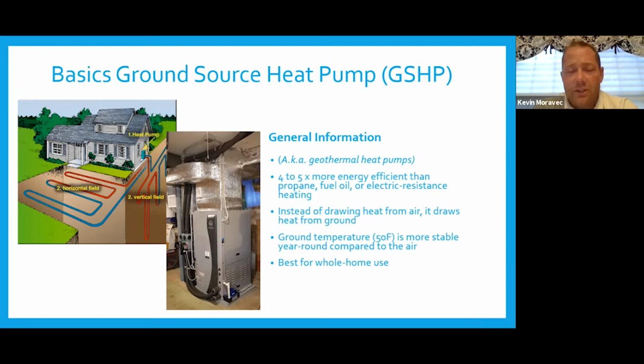The efficiency of the system comes from the amount of energy stored in the ground and how we circulate fluid through that collector system. All we're doing is moving energy from one place, concentrating it, and distributing it. There's no combustion, no waste. It just takes the energy of the compressor and the pumps to move that energy and make it more effective inside your home. That's where you see 4 to 5, in some cases 6 times, the fuel efficiency over propane, fuel oil, gas, and electric resistance.